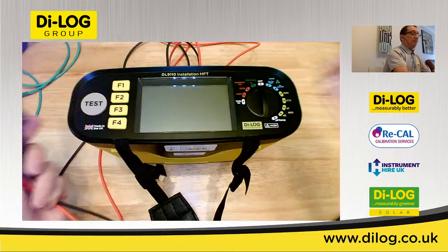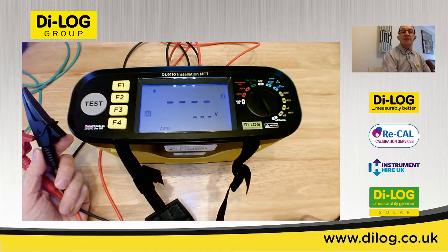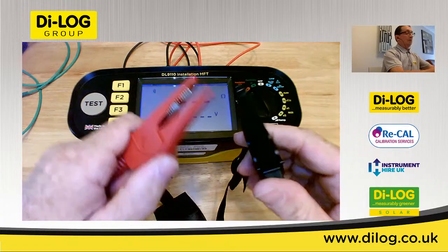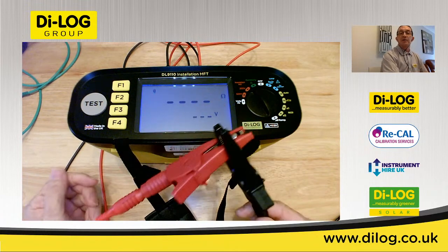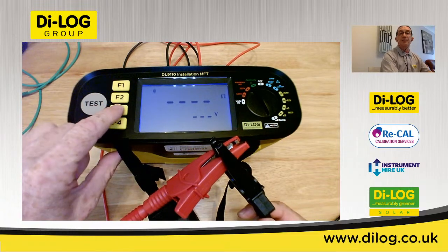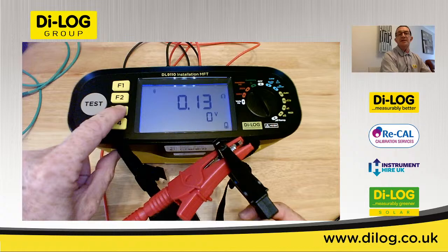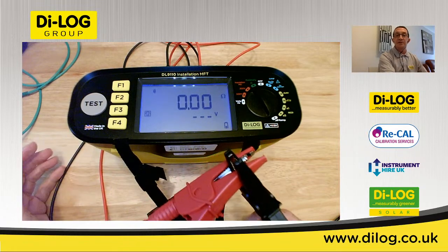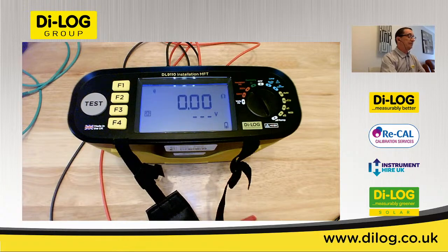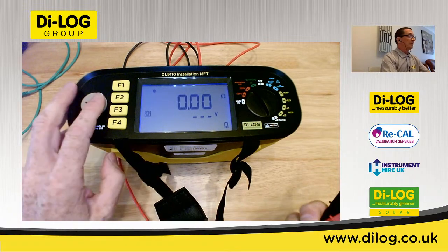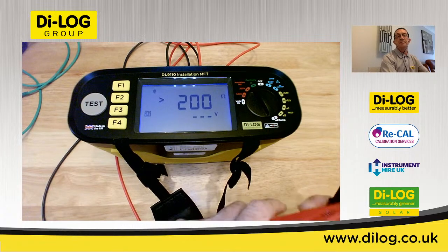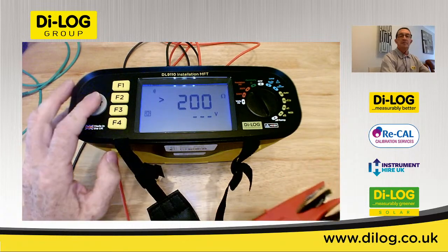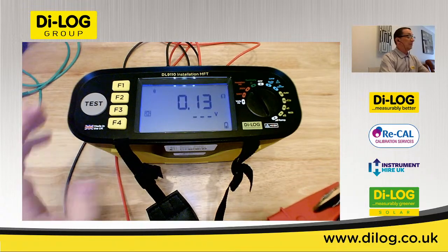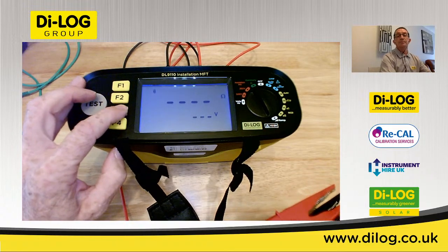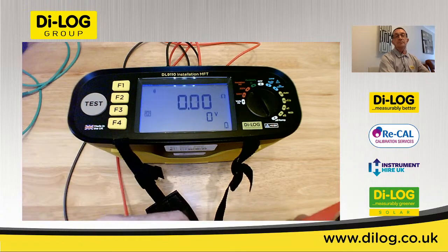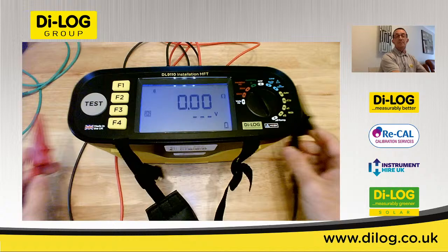Okay, to zero the test leads, put the tester into continuity, put together the crocodile clips, and if we hold down function 3, it begins its test, takes the reading of the leads, and automatically subtracts that from any future values. So take those apart, press the test button, which should give us open circuit, and pop those back together. Sorry, zero the leads. And that's taken that out.